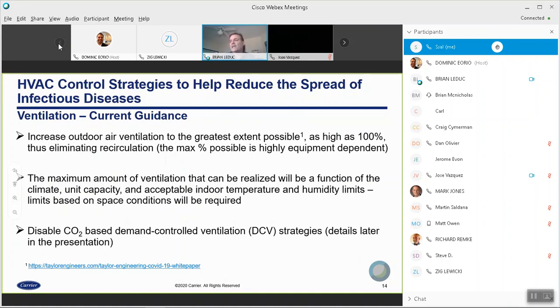Obviously, if you start opening up that outside air damper on a design day above the design ventilation rate, it's going to cost money to cool that air in the summer or heat that air in the winter. There are some voices that are in opposition to some of this guidance, but I thought it was important that you be aware of that in the event that you're discussing this with your customer.